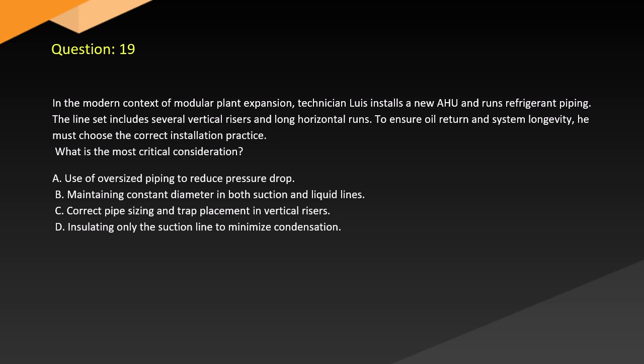A. Use of oversized piping to reduce pressure drop. B. Maintaining constant diameter in both suction and liquid lines. C. Correct pipe sizing and trap placement in vertical risers. D. Insulating only the suction line to minimize condensation.